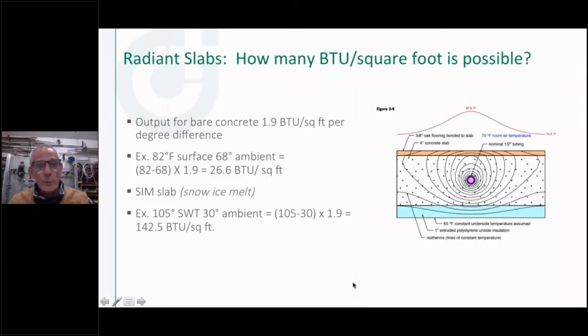So what we want to do now is look at one of my favorite ways to heat a building, a radiant slab. We talked about how many BTUs per square foot is possible in a residential slab. Really the limitation is the surface temperature. You don't want the surface temperature so warm that people in bare feet would be uncomfortable walking on it. I tend to think the mid 70s to high 70s is about right. Everybody's skin temperature can vary a little bit, but usually below 85 degrees, below 84 degrees is probably the sweet spot. Some people say down around 75 to 78.